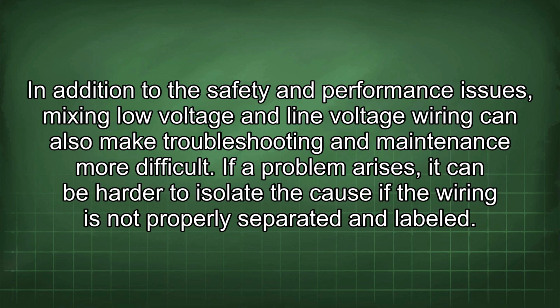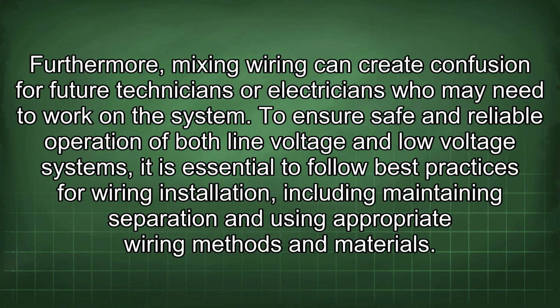In addition to the safety and performance issues, mixing low voltage and line voltage wiring can also make troubleshooting and maintenance more difficult. If a problem arises, it can be harder to isolate the cause if the wiring is not properly separated and labeled. Furthermore, mixing wiring can create confusion for future technicians or electricians who may need to work on the system.